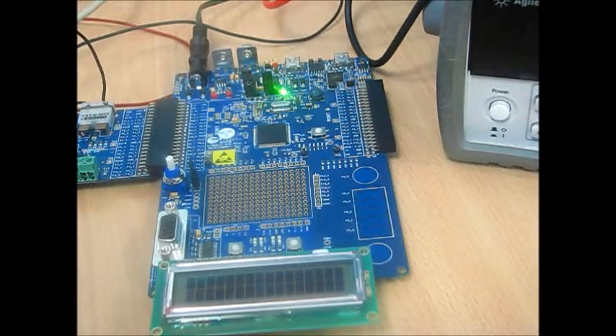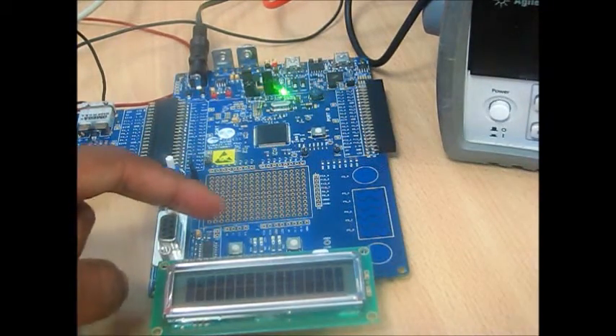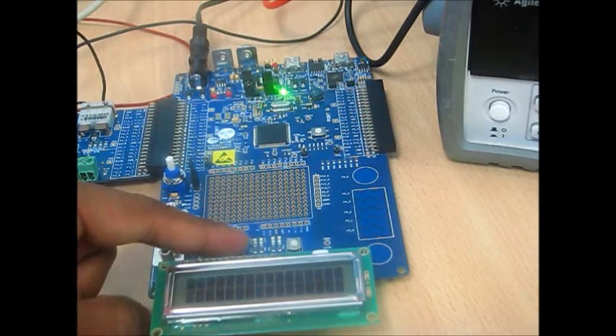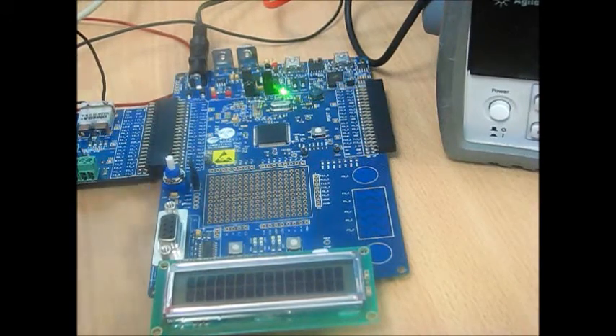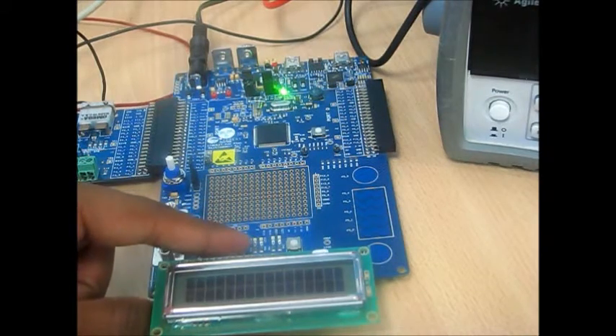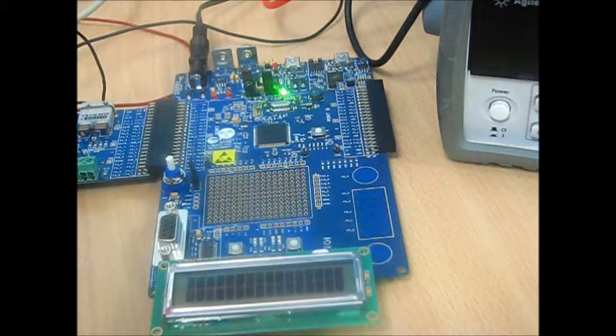Now the device shows the gain calibration constant and the offset calibration constant. To save these values in the EEPROM, press switch 2. Now the values are stored in the EEPROM. To continue, press switch 2. Now the device is calibrated. Let's see the performance of calibration.